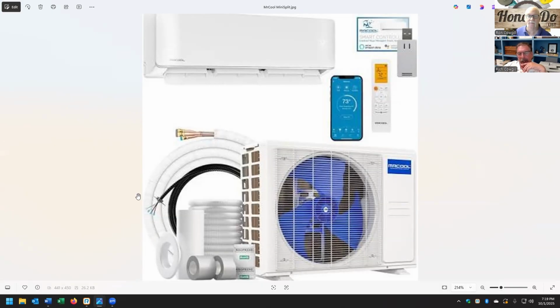Keep in mind, the inexpensive mini splits you can get on Amazon do work, but their performance is going to be sensitive to a few things. Quality of components: the cheaper the unit, the cheaper the components, guaranteed. Correct sizing and selection: if you don't do the sizing properly, don't measure everything, give it all the information, the bigger hammer theory is never correct. If you only need a 1.5 ton, you do not put in a 3 ton.